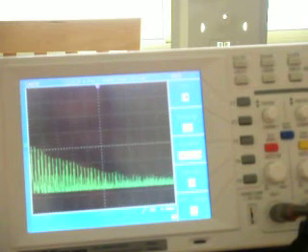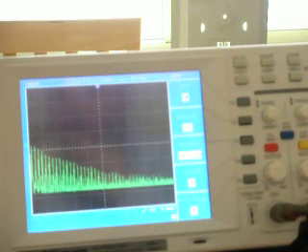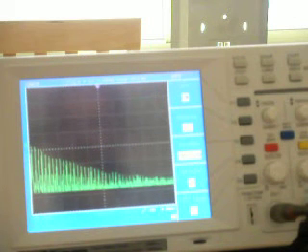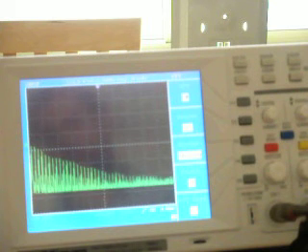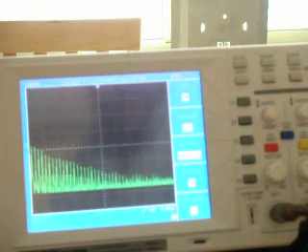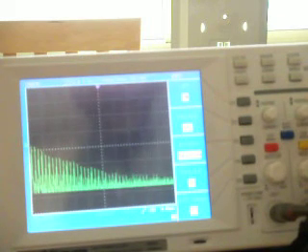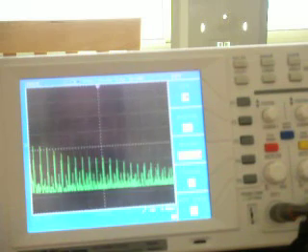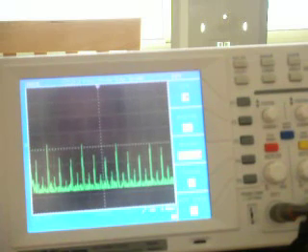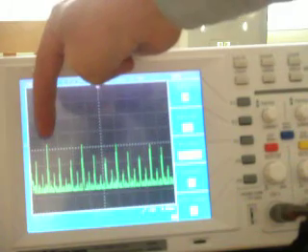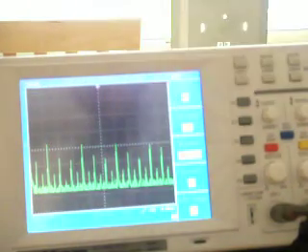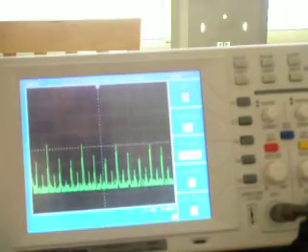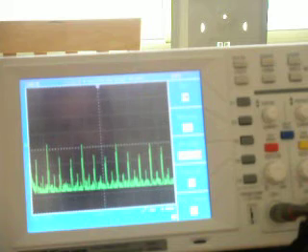Our scale right now is 500 Hz per division in the horizontal direction. You can see that it starts off very high and tails off slowly as the frequency increases. If I expand that out down to 50 Hz per division, you can very clearly see the fundamental frequency which is the 60 Hz right here, and you can see all the additional frequencies. That's very characteristic of electronic products.